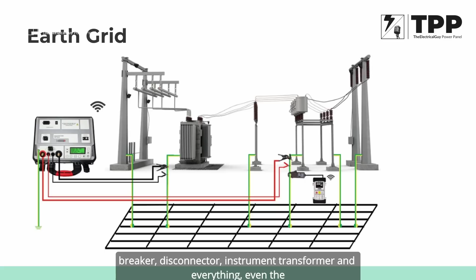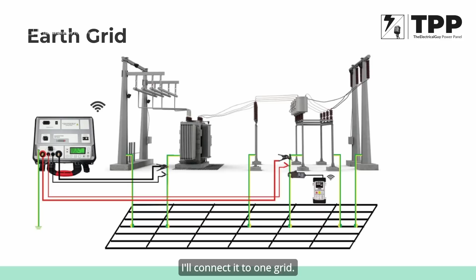Correct, absolutely rightly mentioned, Mandar. So you mentioned three or four different systems. Let me summarize: I'll take all the non-conductive parts in the substation. If it's an outdoor substation, the support structures of all equipment like circuit breakers, disconnectors, instrument transformers, and even the marshalling boxes, I'll connect to one grid. Maybe it could be a mesh underneath the earth, or maybe a well, and I'll give all the connections there, right?